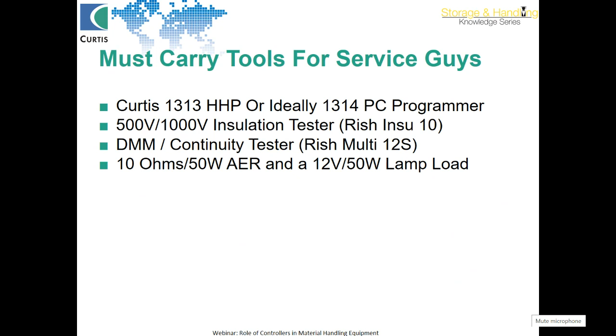Insulation tester should be there. These are only the recommended tools with the recommended brands. Digital multimeter or continuity tester for the cables. Then a lamp load or a 10 ohm 50 watt resistor. It is good to have in your toolkit to discharge the battery before touching the live terminals on the controller.